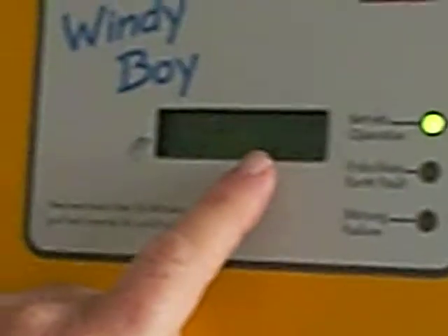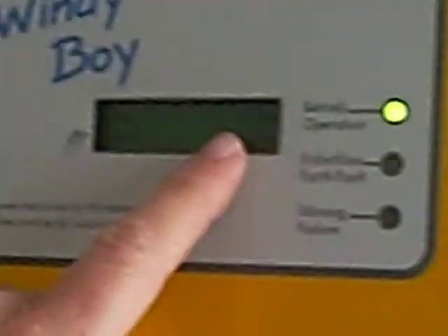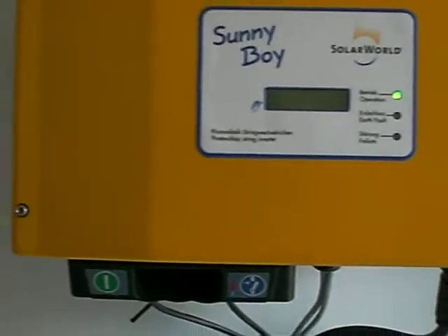Under normal conditions, if there's power being generated here, it goes in and synchronizes. These 2 units synchronize automatically. These are the control units, the Windy Boy. You will see at the moment we have generated 2.33 kilowatt hours so far today. At the moment we're generating 250 watts. Similarly on that one, I'll show you if there's any energy still being generated from the solar panels. So these 2 synchronize to the grid, and to that unit.